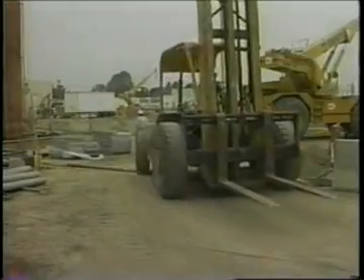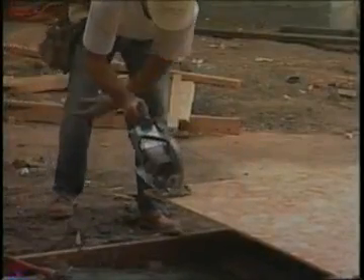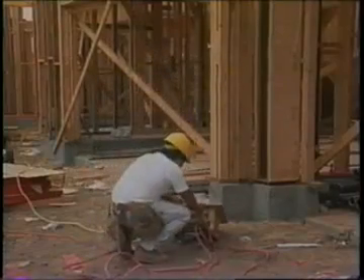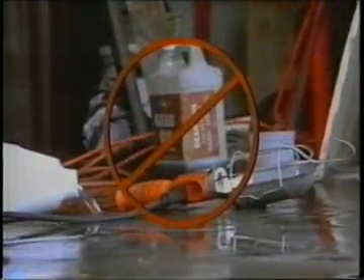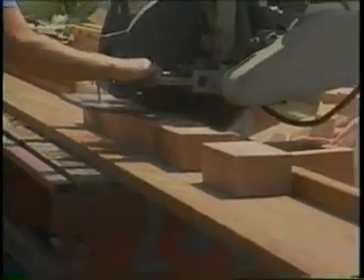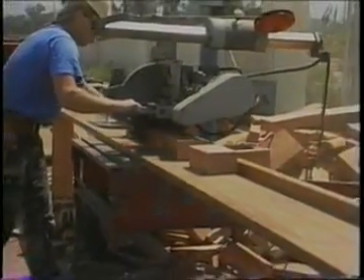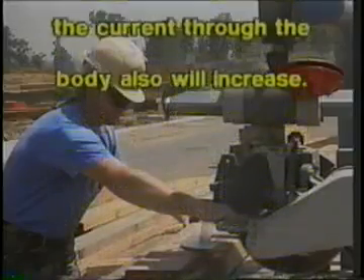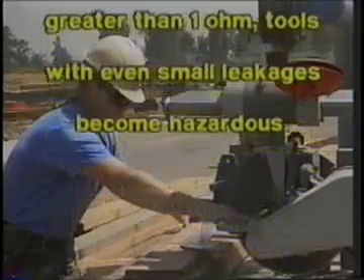Flexible cords are more vulnerable to damage than fixed wiring. Flexible cords must be connected to devices and fittings so as to prevent tension at joints and terminal screws. Because a cord is exposed, these terminals become more vulnerable. Improperly connected terminals is another common situation. When a cord connector is wet, hazardous leakage can occur to the equipment grounding conductor and to humans who pick up that connector if they also provide a path to ground. Such leakage is not limited to the face of the connector but also develops at any wet portion of it. When the leakage current of tools is below 1 milliampere and the grounding conductor has a low resistance, no shock should be perceived. However, should the resistance of the equipment grounding conductor increase, the current through the body also will increase. Therefore, if the resistance of the equipment grounding conductor is significantly greater than 1 ohm, tools with even small leakages become hazardous.